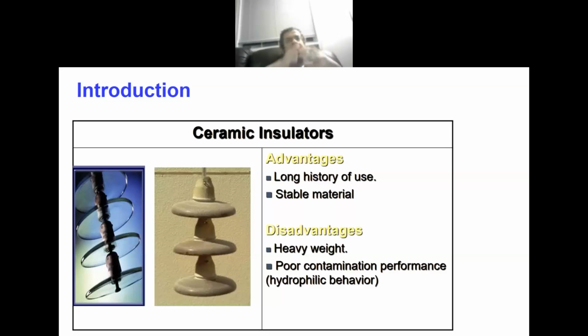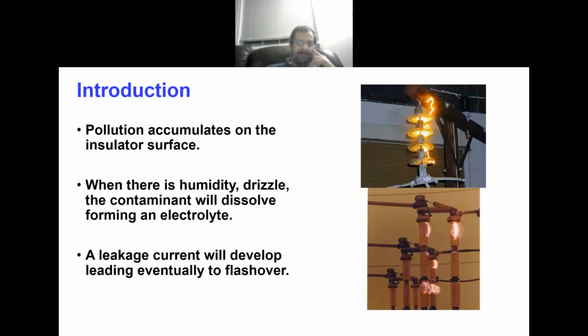Insulators are subjected to the environment, so there will be a lot of pollutant on the surface. Humidity and pollutant, especially if the insulator is near the sea or coast, will contain salt like NaCl, which starts to dissolve because of the water. This creates a perfect environment to start conduction between the high voltage and the ground, leading to flashover.